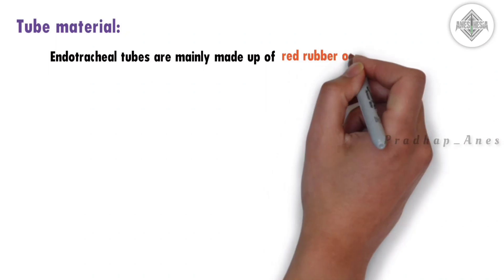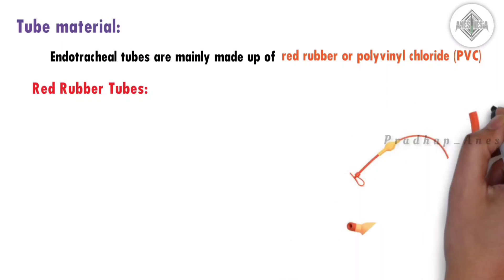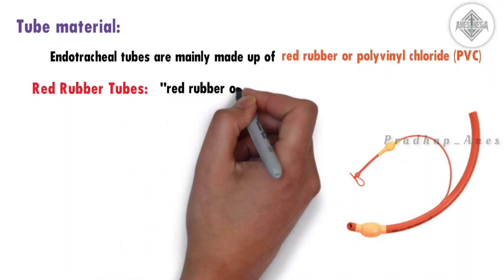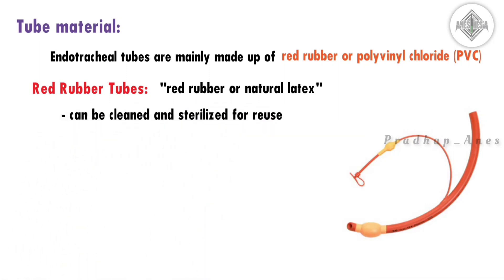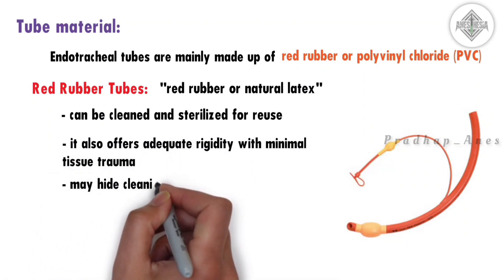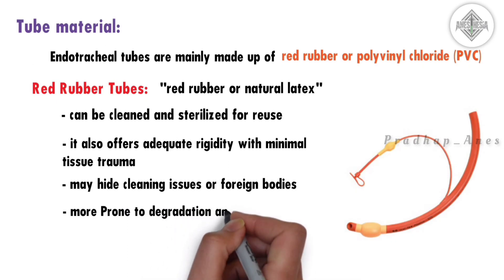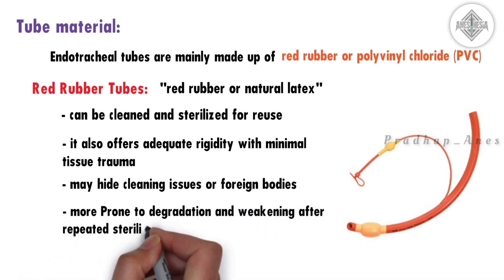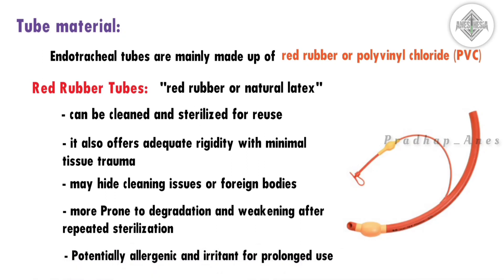Next, we'll look at tube material. Endotracheal tubes are mainly made of red rubber or PVC. Red rubber tubes are made from natural latex and can be cleaned and sterilized for reuse. They offer adequate rigidity with minimal tissue trauma. However, red rubber is non-transparent, which may hide cleaning issues or foreign bodies, and the tube is prone to degradation after repeated sterilization. The material is also potentially allergenic and irritant for prolonged use, which is why it has largely been replaced.